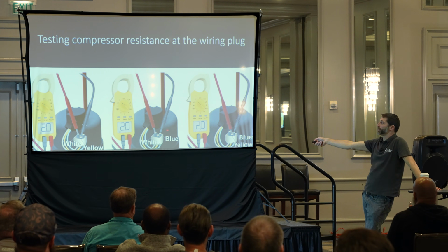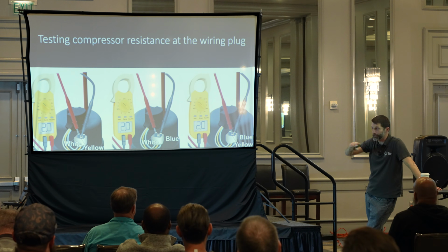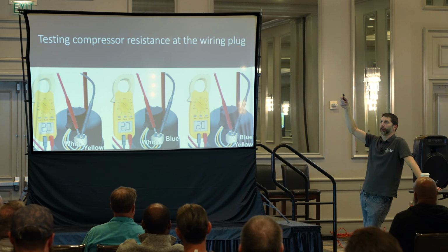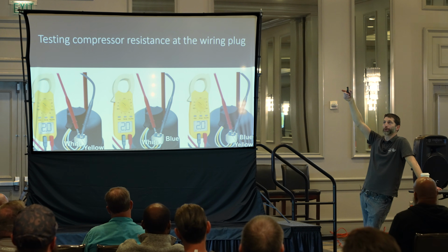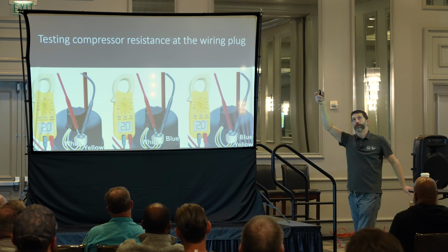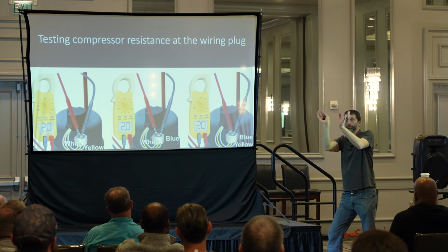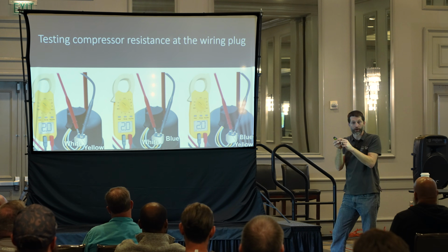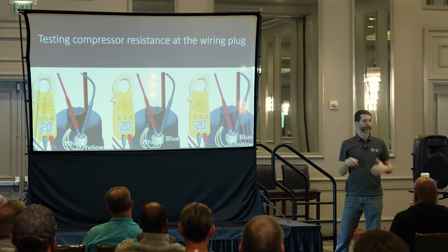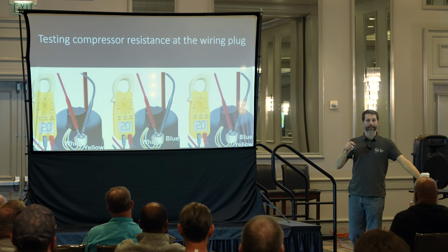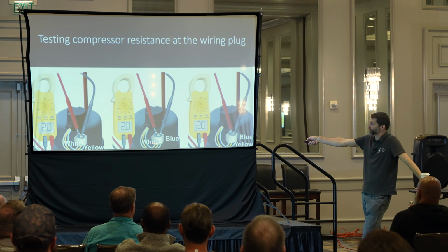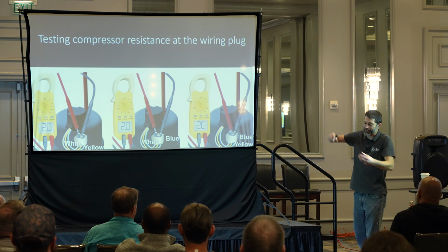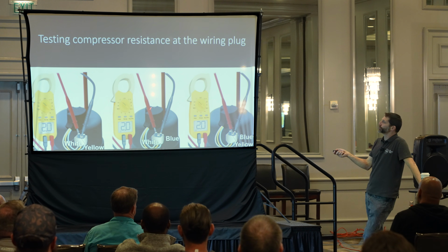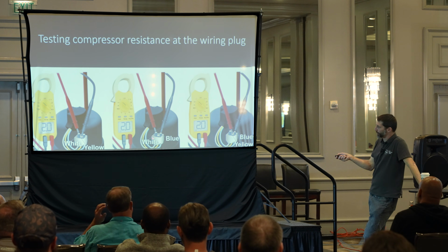Some equipment manufacturers have little indents on the spade terminals, and you have to squeeze the spade terminals with the crimp connectors to release the tab in order to pull the terminal off. Don't just yank on it, you will break the spade terminal right off the circuit board. Some have different things like that going on, but some just have a little wiring harness you can disconnect. So you're not going to go straight here, you're going to go to the wiring harness plug and check your electrical resistance.